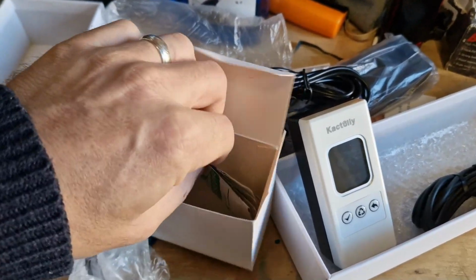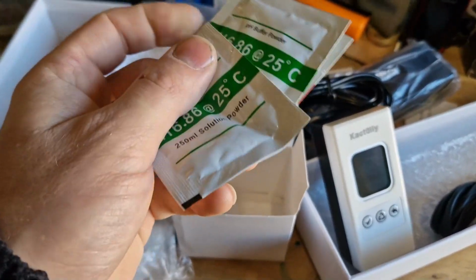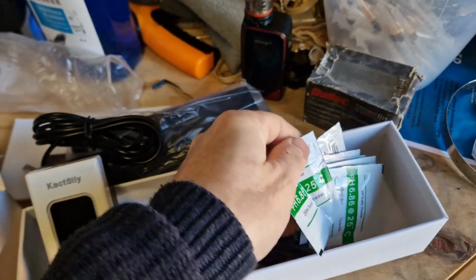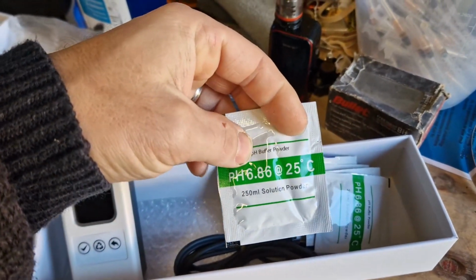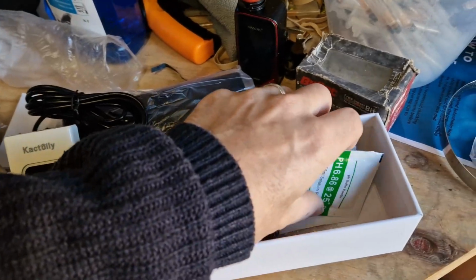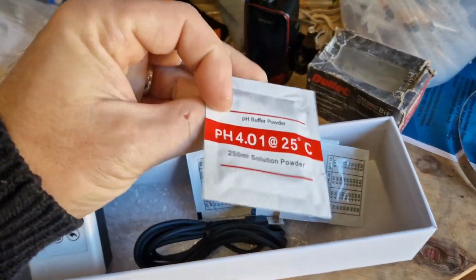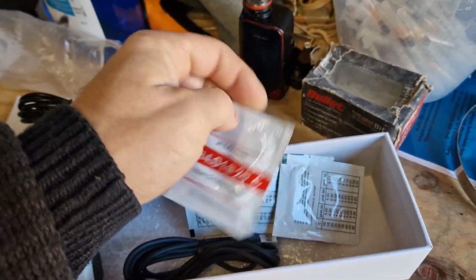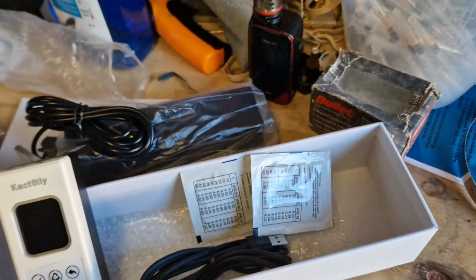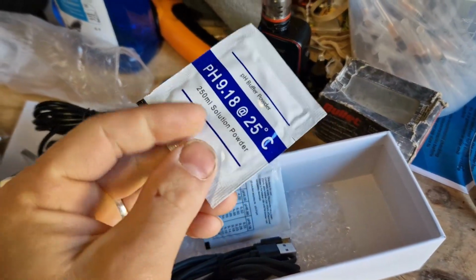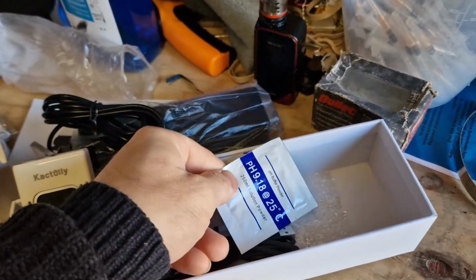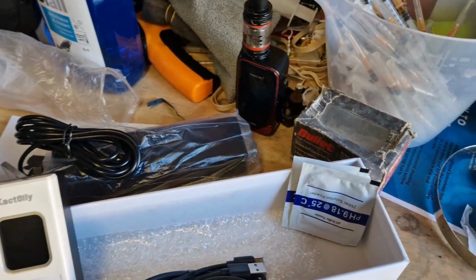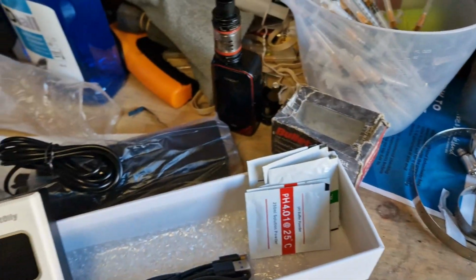And then we've got calibration solutions. So we've got a pH 6.86. We've got a pH 4.01, another 4.01, and a pH of 9.18. So it's a three-part calibration, which should give you even more accuracy on your pH readouts.